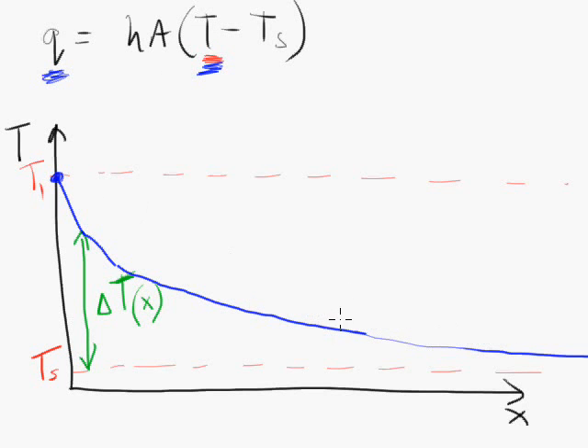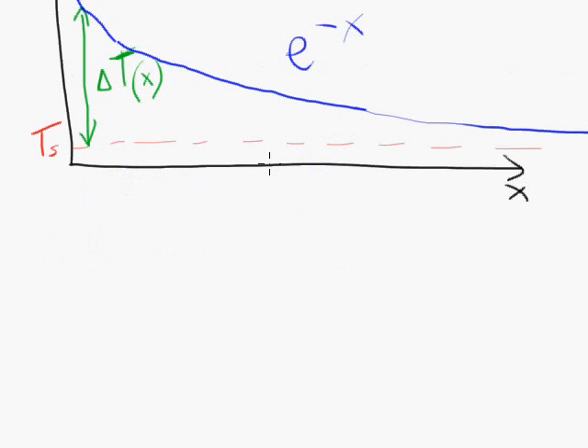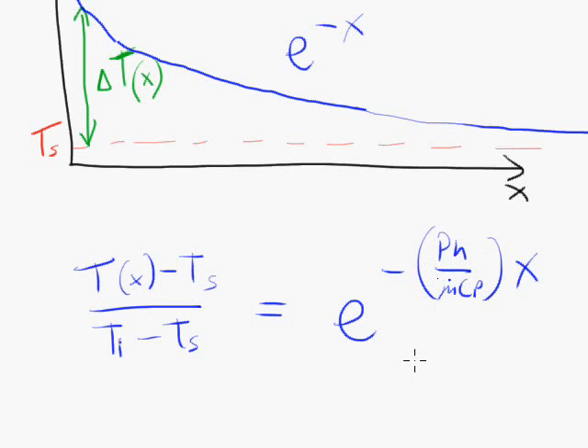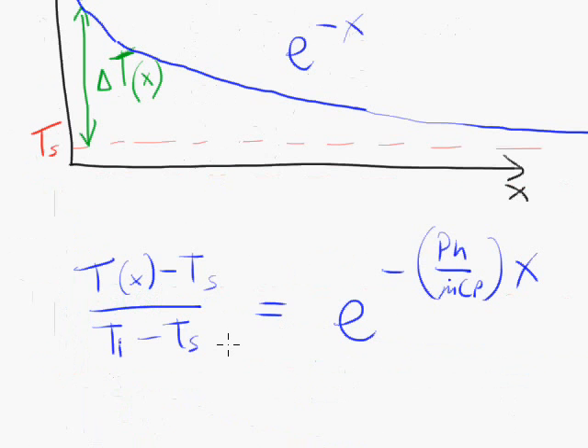Now if you look at the shape of this curve, you can kind of argue on physical grounds that this is what the shape should be. Mathematically, if you look at that curve, it looks like e to the minus X. And it turns out that we can prove that it is an e to the minus X type curve. And the full detail of that is the temperature of the fluid minus T S divided by the inlet temperature, T i minus T S, is equal to e to the minus p H over M dot C P times X. M dot is the mass flow rate of the fluid. C P is the specific heat of the fluid. P is the perimeter of the pipe cross-section. So for a circular pipe, P is the circumference of the circle. T i is the inlet temperature. T S is the pipe surface temperature.